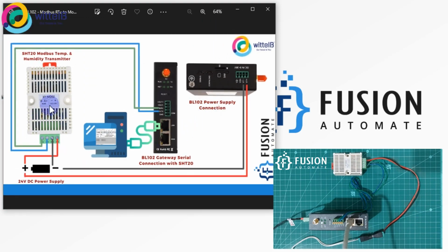To power up this transmitter, we have also given the 24 volt DC power supply to this transmitter. So both these devices are powered up with the 24 volt power supply, and this transmitter device is connected serially to this gateway with two cables. The cable color is green for B minus and blue for A plus, as you can see here in the video as well. Now our agenda is to convert Modbus serial data into Modbus TCP data. Let's see how we can do that.